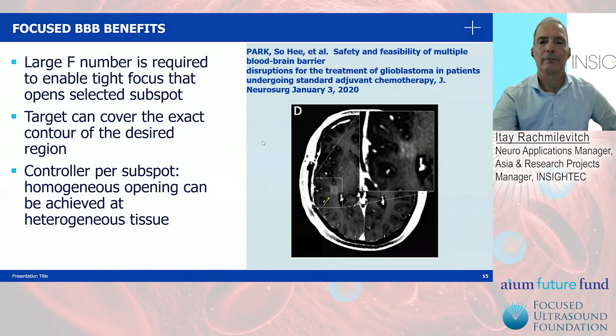Basically, what we do here is we wanted to solve the problem that we cannot place a hydrophone into the patient's head. Because in experiments, we place a hydrophone, we use ACT maps, acoustic correction table, maps that we read, we put them back, and then we know what is the best phase correction. Otherwise, we use the CT, where we have written the models, our team, myself included too, that can calculate the phase correction based on the CT and see for more or less best phase correction.